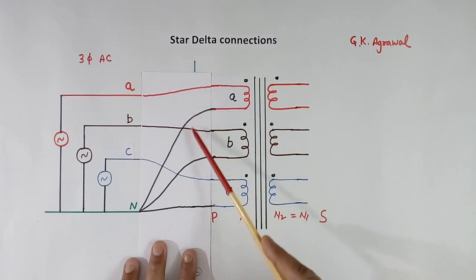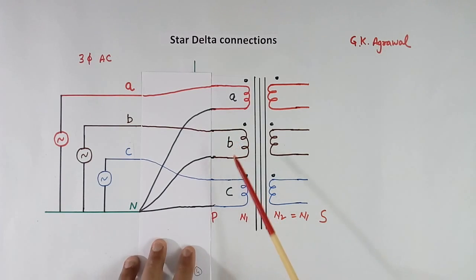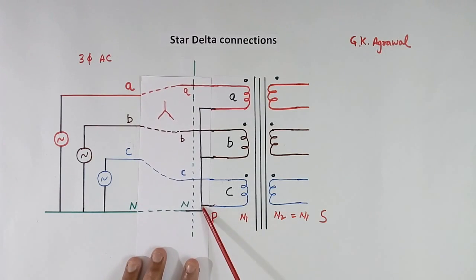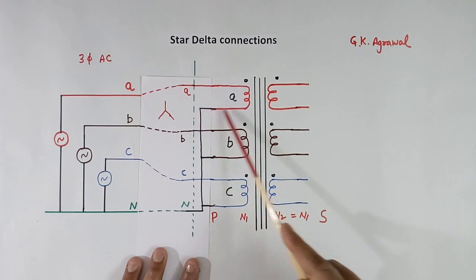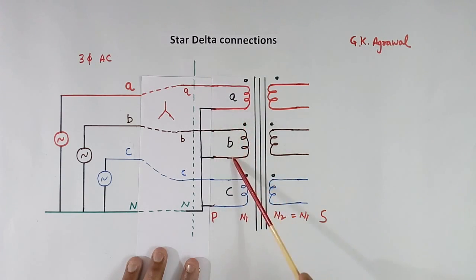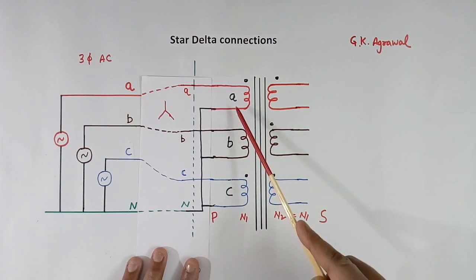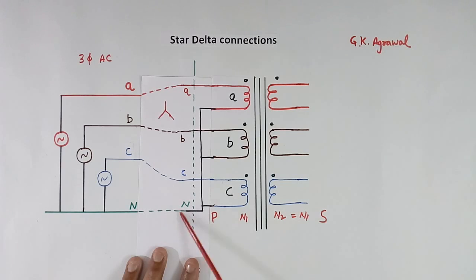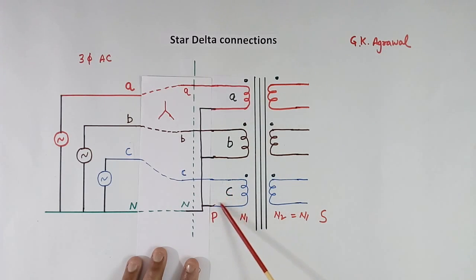If you want to connect the transformer only in star mode, there is another way. The transformer manufacturer connects the other terminal of the 3 phases — A, B, C — inside itself, so only 1 neutral wire comes out. You get 4 wires: A, B, C, and neutral. But in this way, you can connect this winding only in star, not in delta mode.